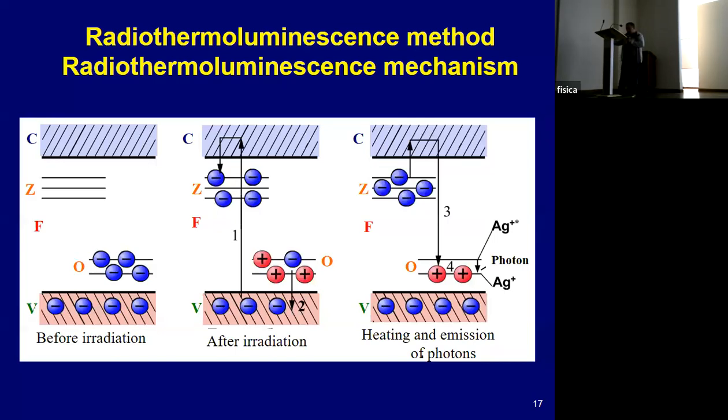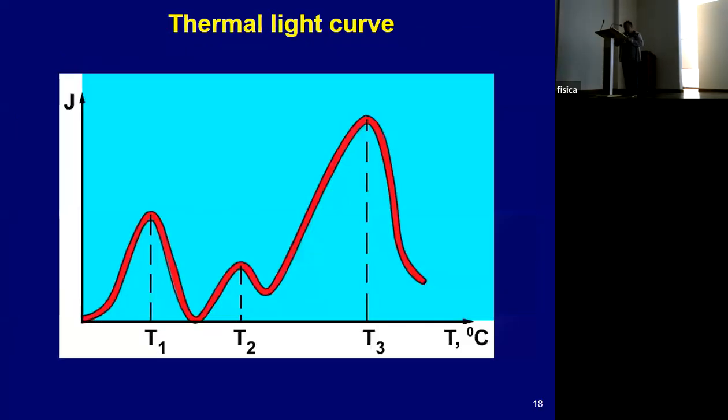A distinctive feature of thermoluminescence is the destruction during heating of the centers created under the action of ionizing radiation. Therefore, after the measurement procedure, the thermoluminescent dosimeter loses information about the radiation dose and can be used for the next user. The glow of thermoluminescence serves as a measure of the dose of ionizing radiation absorbed in the detector.